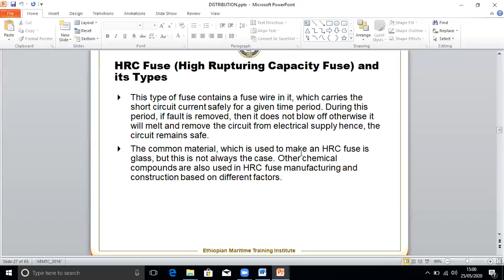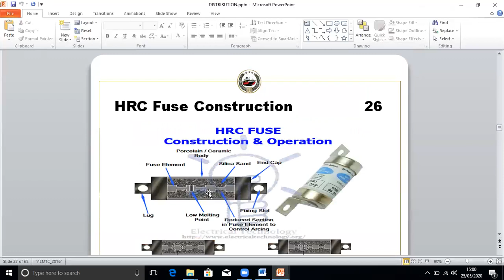The common material which is used to make an HRC fuse is glass, but it is not always. It uses chemical compounds also. So this is called the HRC fuse. These are called the lugs, that is this one, and this has to be fixed with a screw here. There are two screws here. Here you can see how many amps it is, and inside is the fuse element. So they put the fuse element, then some ceramic body, silica sand, end cap. This is called HRC fuse, high rupturing type fuses.